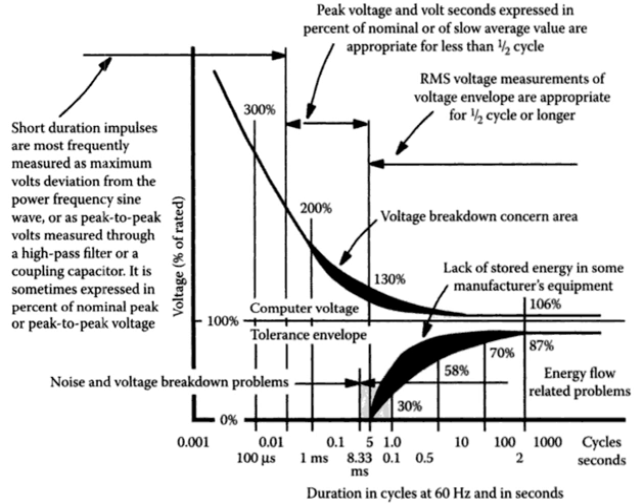Electric power quality, or simply power quality, involves voltage, frequency, and waveform. Good power quality can be defined as a steady supply voltage that stays within the prescribed range, steady AC frequency close to the rated value, and smooth voltage curve waveform resembles a sine wave. In general, it is useful to consider power quality as the compatibility between what comes out of an electric outlet and the load that is plugged into it.